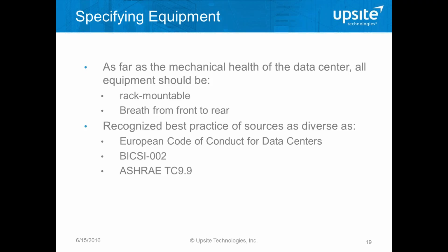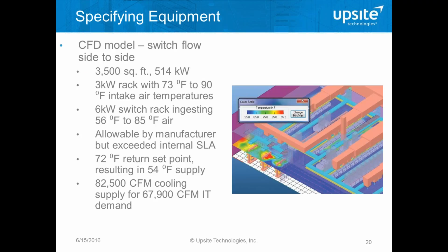So we can look at an example, a case study that I actually worked on a few years ago, on the next slide that kind of walks us through this. So we started with this data center, about a half a megawatt, and we had an entrance room, a point of presence here with open racks in a cage, and we see that we have inlet temperatures ranging from 73 to 90 degrees. And then out in the middle of the floor, we had a core switch and some storage cabinets that were breathing side to side and front to top, and we were getting 56 to 85 degree inlet temperatures.